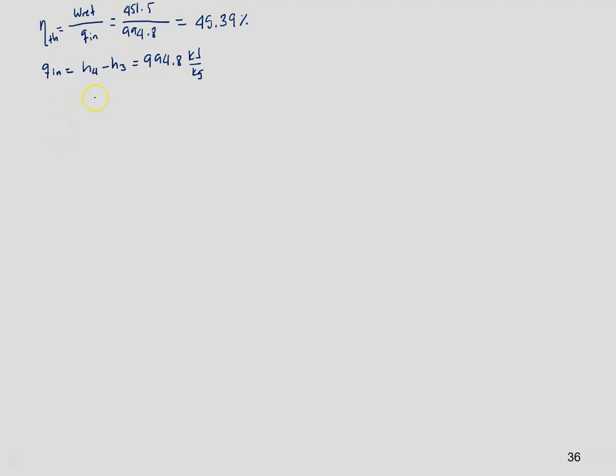Now we can get the overall efficiency. The expression is: thermal efficiency equals net power divided by q_in, times the electrical efficiency — electrical power divided by the mechanical net power. These net power terms cancel, so we just multiply 0.4539 (the thermal efficiency) times 0.96 (the generator efficiency), which gives 43.57 percent.